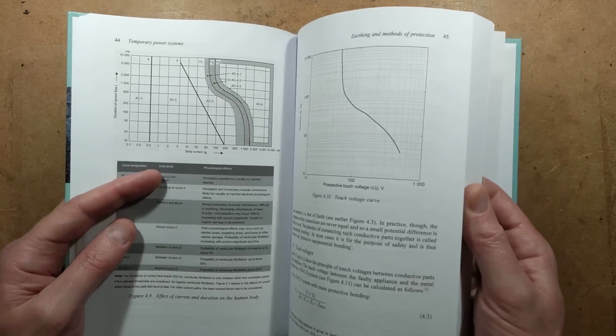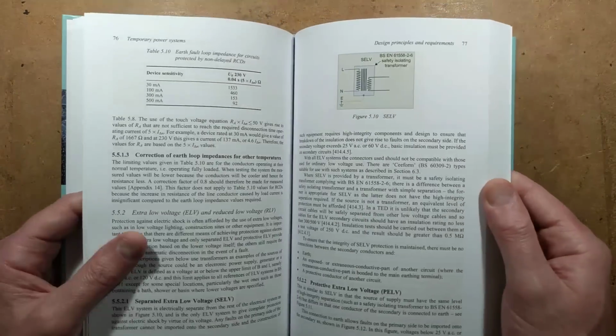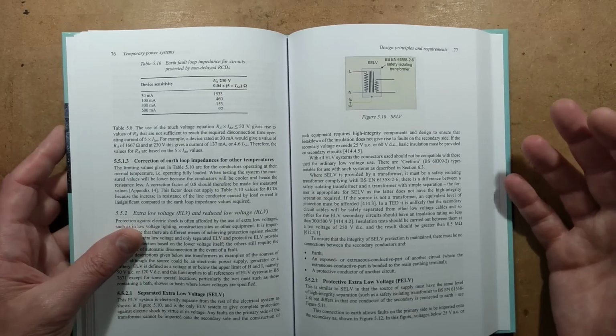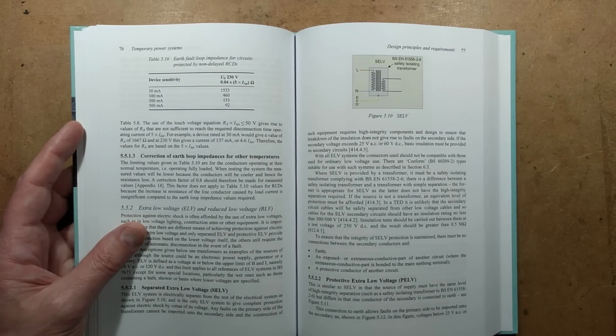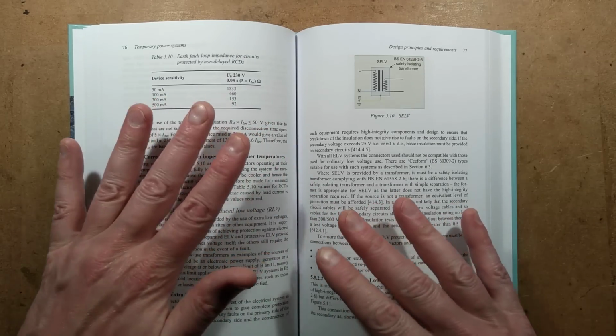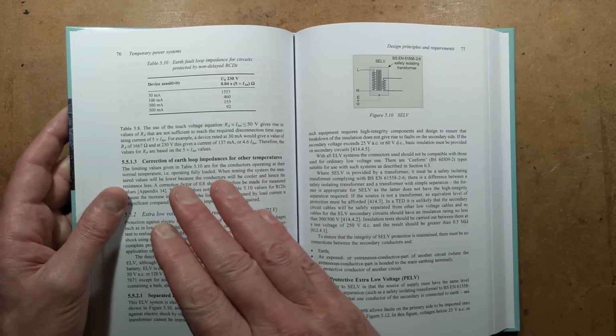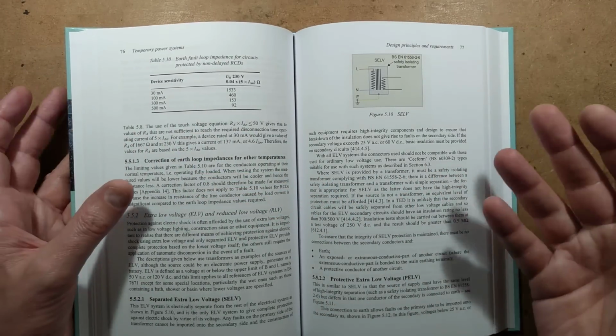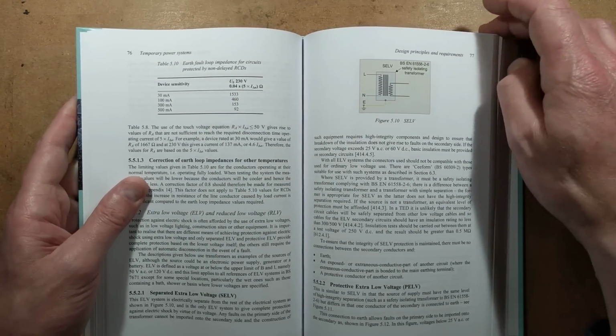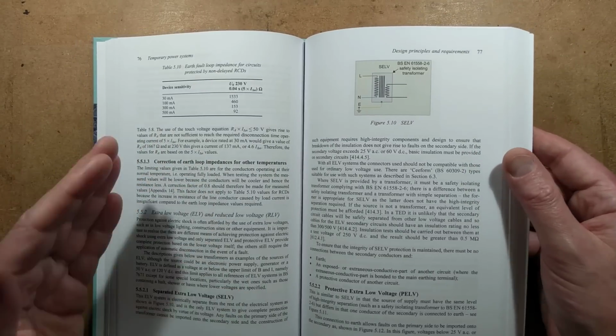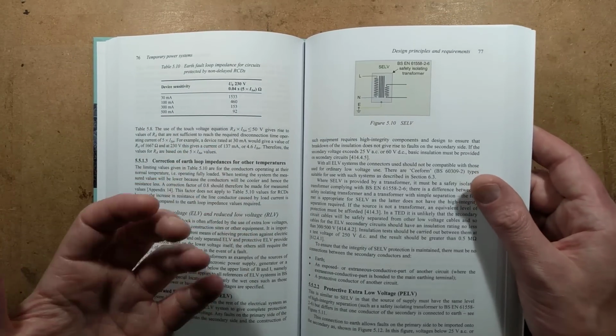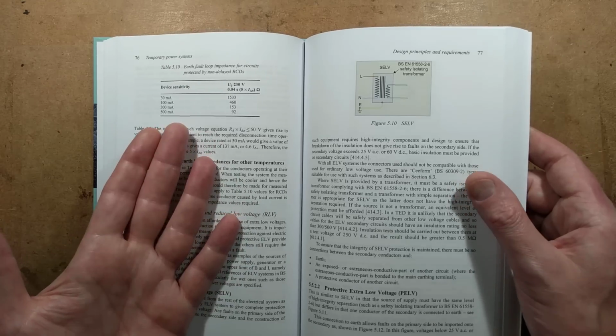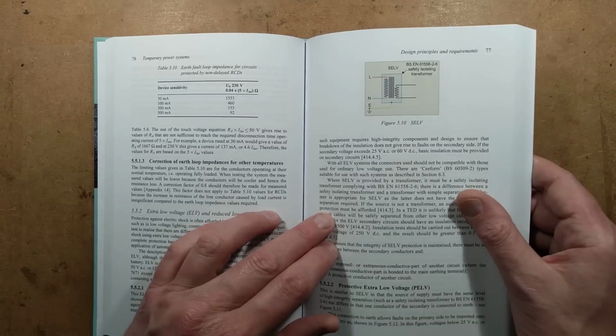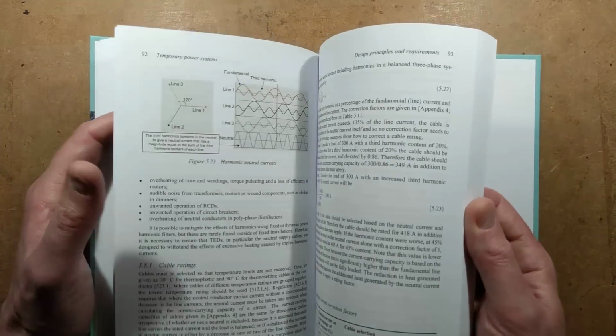But the book is a guide to everything about supplies and the problems associated with if you've got a generator and you run it into a building, and there's any cross-bonding between the earth between those buildings, you have to know what type of supplies come into the other building to determine the wire size for proper safety protection. Because in some instances with certain electrical systems, you can get the full building's supply current going through the earth wire. And if you've got a generator with an earth electrode, then that's not that great.